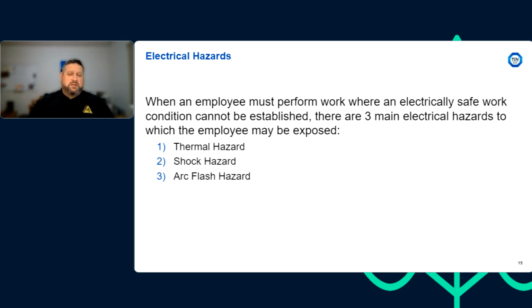So there's a lot of thermal energy there, but it's not quite to the level of a shock hazard or even close to an arc flash hazard. A shock hazard comes into play depending on which standard we're using. In Canada, we consider it whenever we exceed 30 volts AC or 60 volts DC. Same with our friends in Europe. In the United States, if we're complying with OSHA, they say 50 volts for everything, AC or DC. NFPA 70E, one of the most up-to-date standards, recognizes 50 volts AC as a shock hazard and 100 volts DC as the level for battery shock hazard.